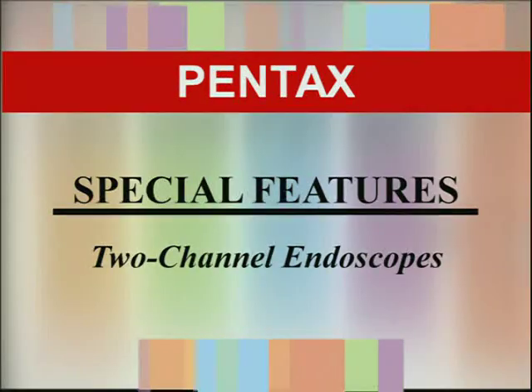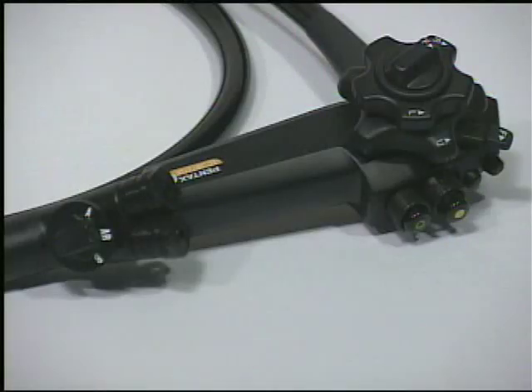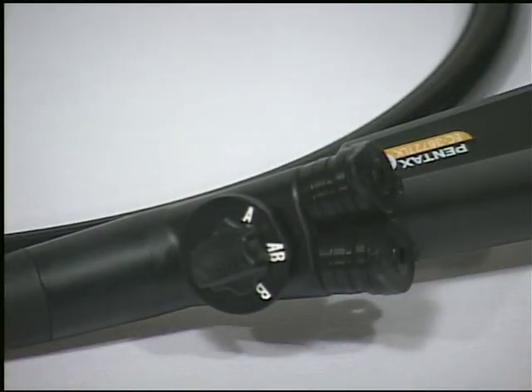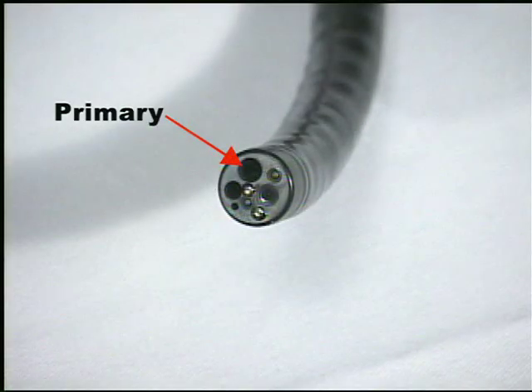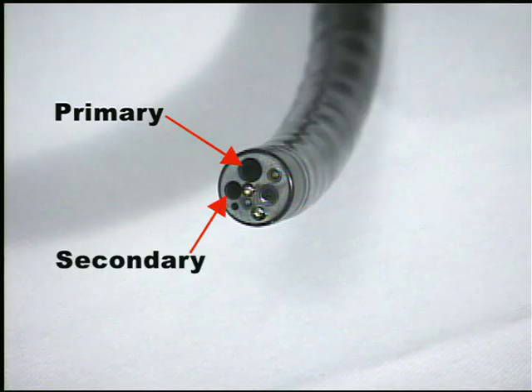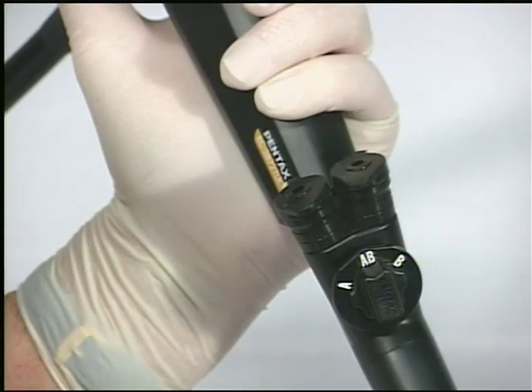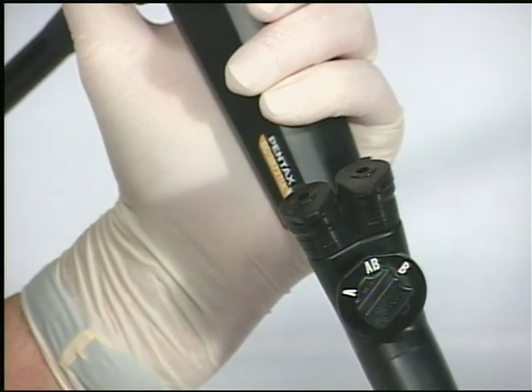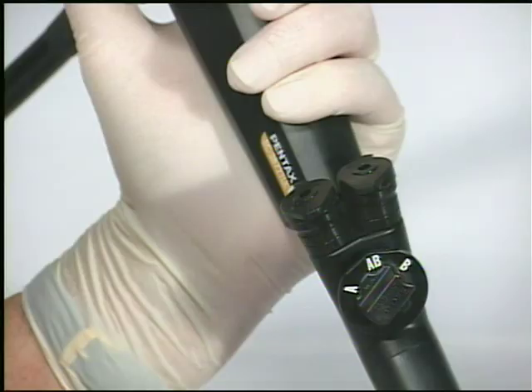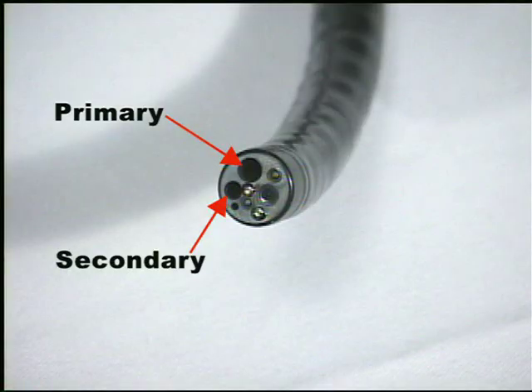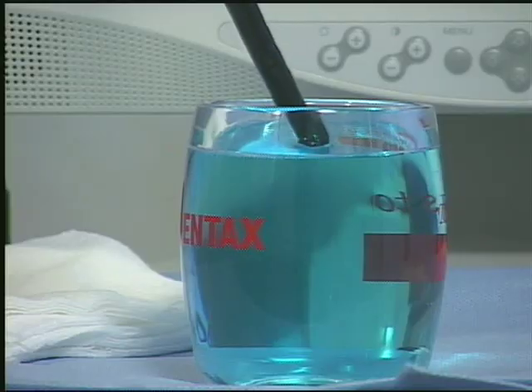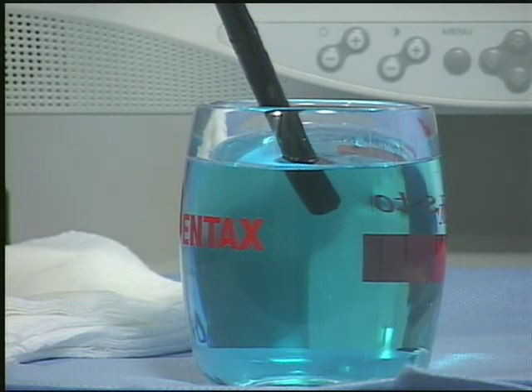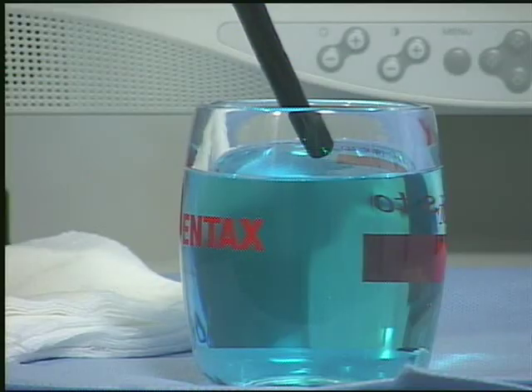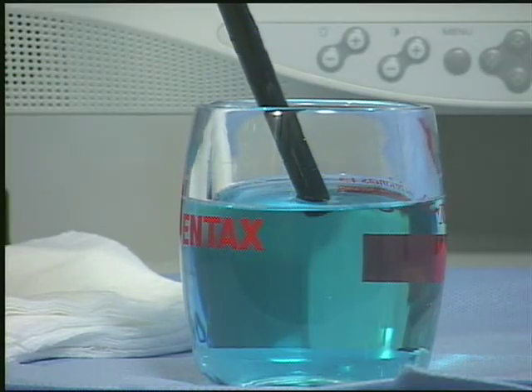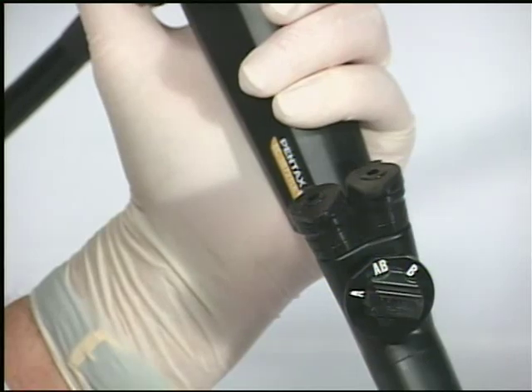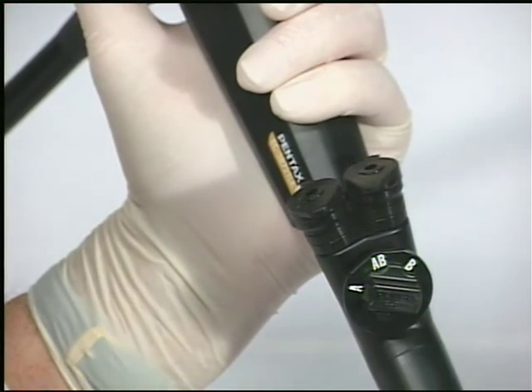Two-channel endoscopes. The most popular Pentax colonoscope features two independent instrument suction channels, a primary larger biopsy channel and a smaller secondary instrument suction channel. A special suction selector mechanism allows the user the choice of suction through either channel or simultaneous suction through both primary and secondary channels. During pre-cleaning of the two-channel colonoscope in the examination room, enzymatic detergent solution should be suctioned through both instrument suction channels using the instrument selector mechanism to direct suction to each separate channel.